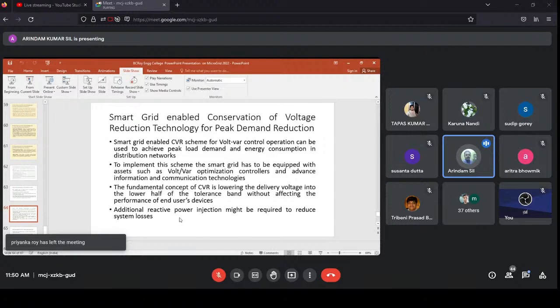The fundamental concept of CVR is lowering the delivered voltage into the lower half of the tolerance bandwidth without affecting the performance of end users' devices, and additional reactive power injection might be required to reduce system losses.